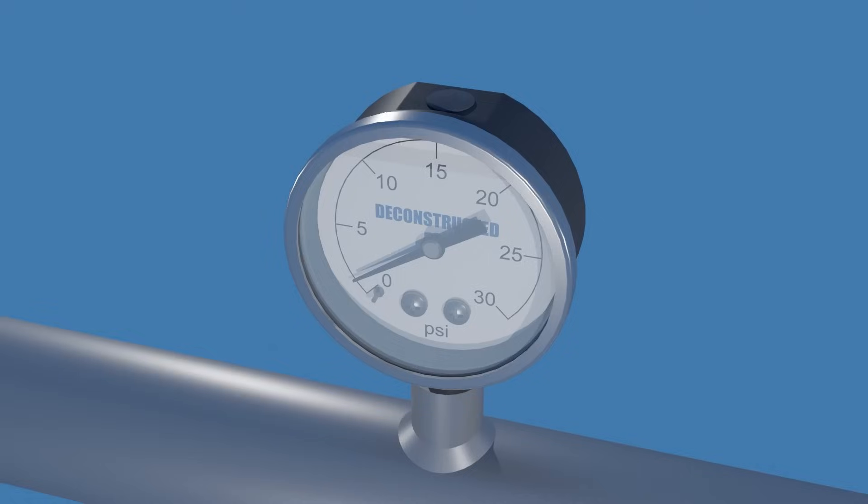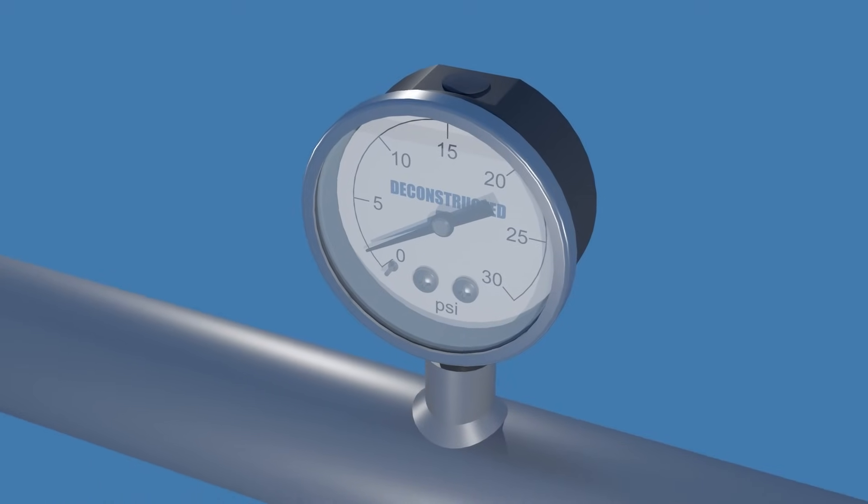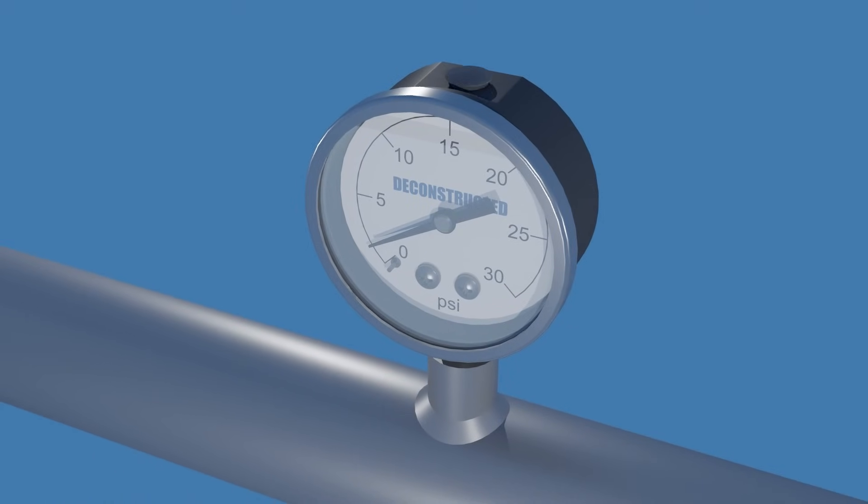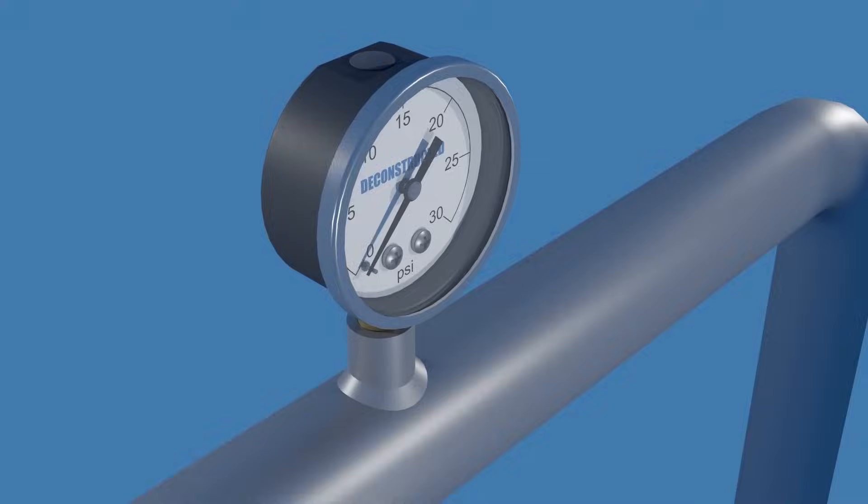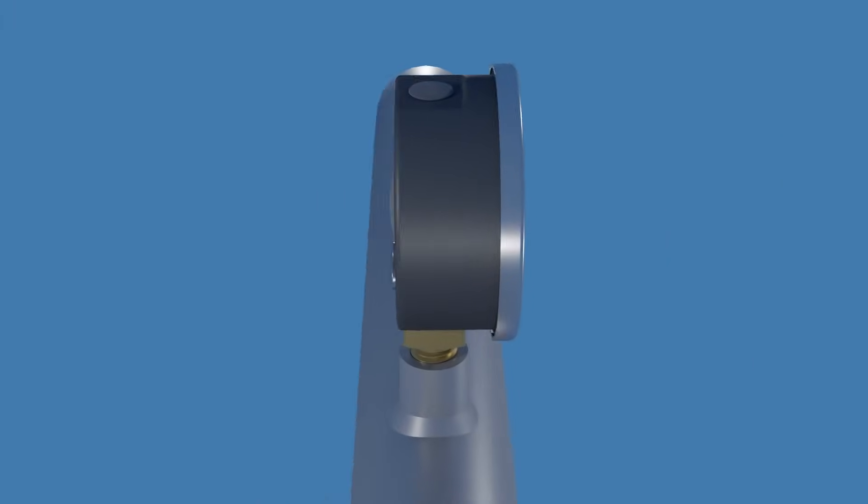Temperature variations during shipment and operation can cause the liquid fill to expand and contract, changing the pressure inside the sealed case, which can reduce the accuracy of the reading. Venting is sometimes required to release excess pressure. We will look at the reasons we use dry versus liquid filled gauges in more detail later in this video.